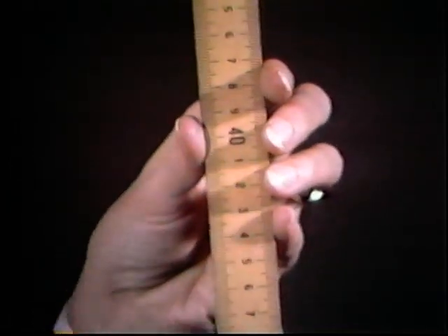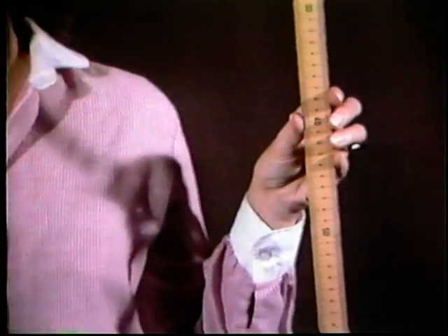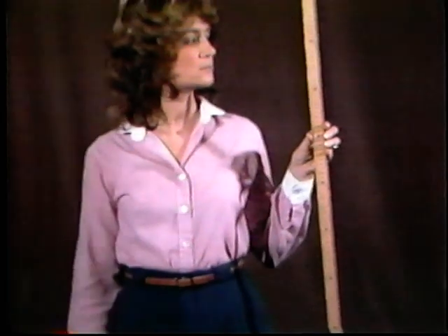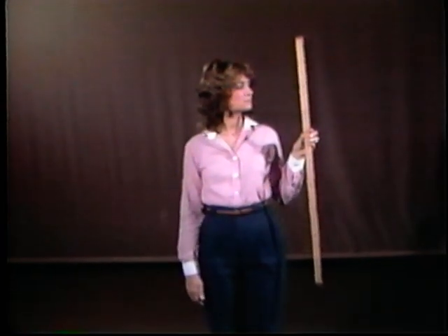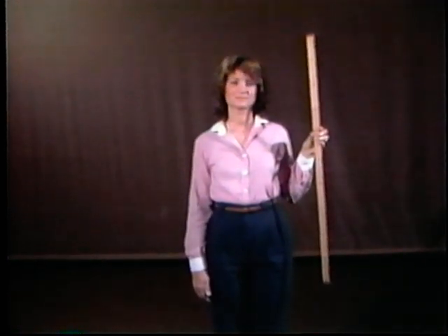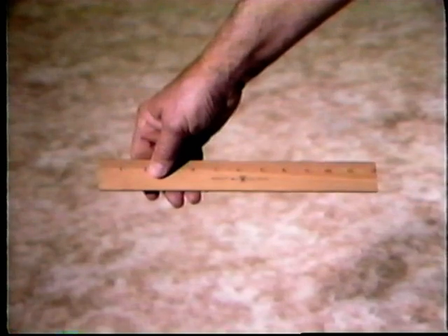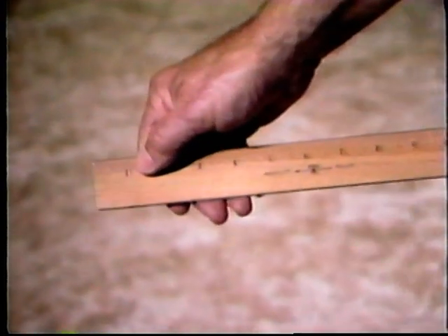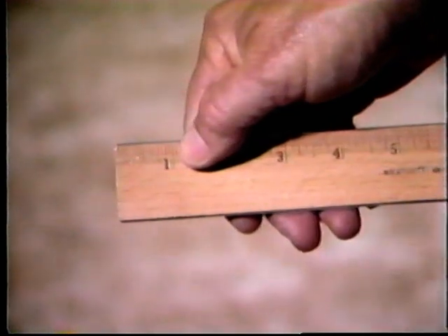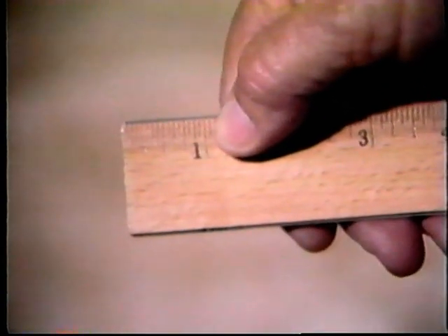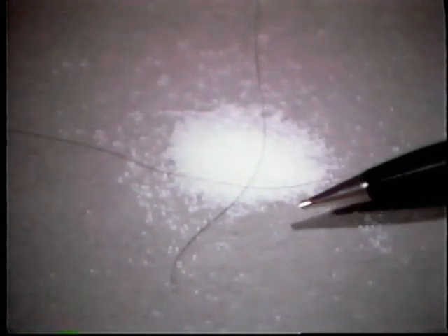The unit of measure is the micrometer, which is also referred to as a micron. And it equals one millionth of a meter. That is one millionth of the length of the rod that is being held here. One micrometer is equal to 39 millionths of an inch. So a micrometer is very small. One grain of table salt measures 100 micrometers. This human hair here, about 70 micrometers. And many of the particles in the air in a pneumatic system are even smaller than this.